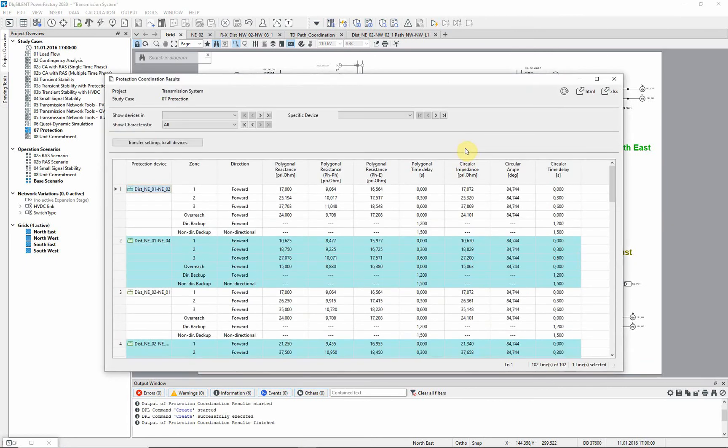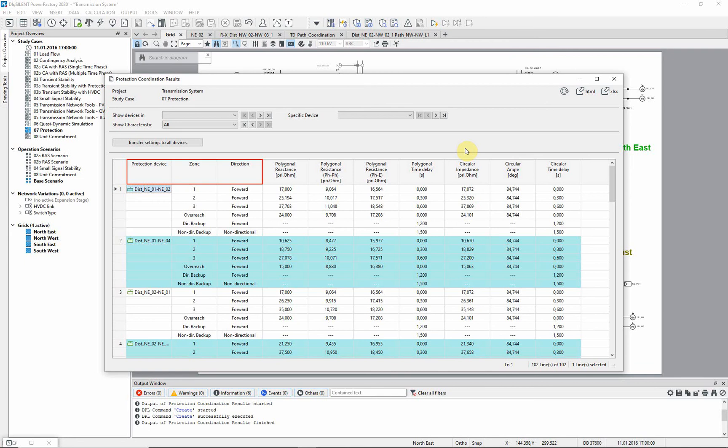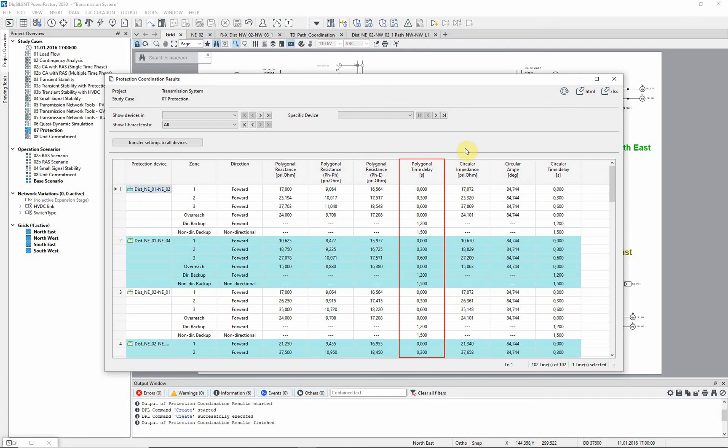After executing the assistant, a table report detailing the calculated settings is shown. In the first three columns, the device, stages and directions of the implemented relay are shown, followed by the reach and timer settings. You can see that the time settings clearly follow the rules set in the assistant.